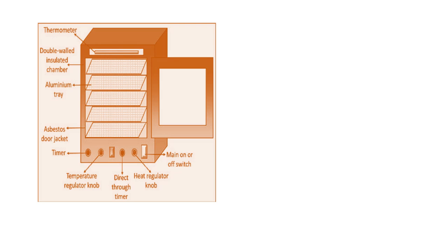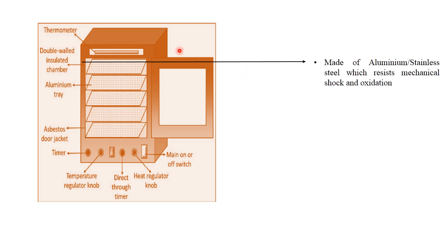Let us check the parts of a hot air oven. This one is the thermometer that will record the temperature. This hot air oven is made up of a double-walled insulated chamber, and it is either made up of aluminium or stainless steel, which resists mechanical shock or oxidation. In between this double wall there is presence of an insulated layer of glass wool. Inside there are perforated aluminium trays where articles that need to be sterilized are placed.